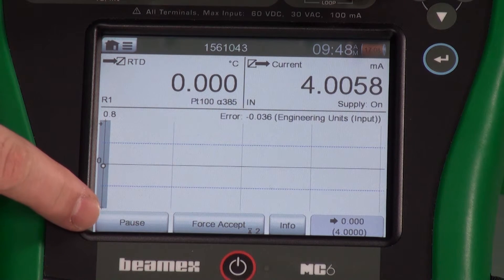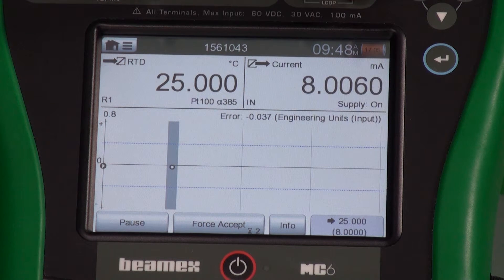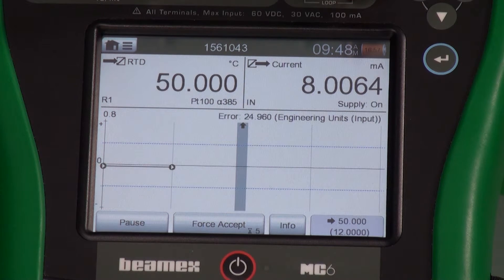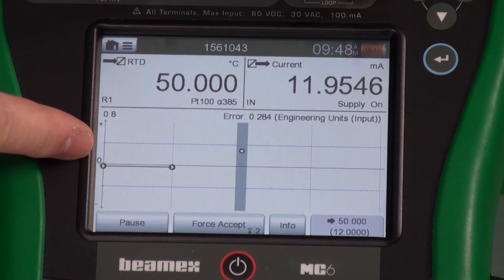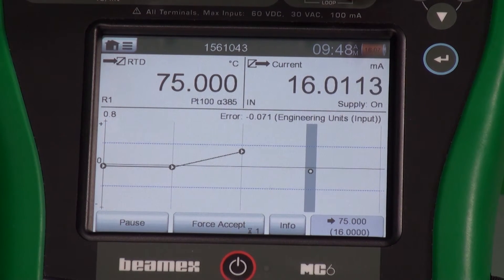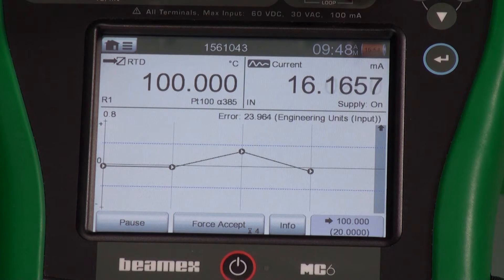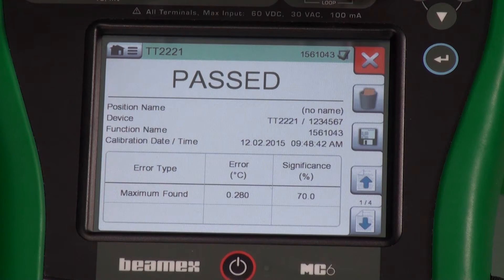Let's press start. We do have the option at any time to pause the calibration — maybe one of the leads might pop off. That's a good time to pause it, reconnect, and restart. Look at the graph — the zero. If the dot is on there, that means it's passing. The blue lines above and below are our tolerance. We've got a dip in the midsection, but overall everything's green.